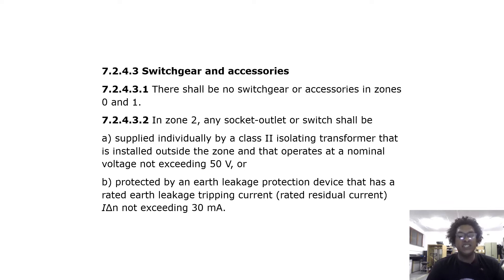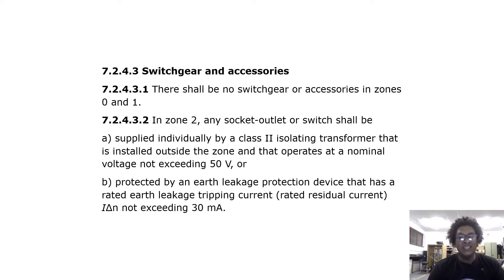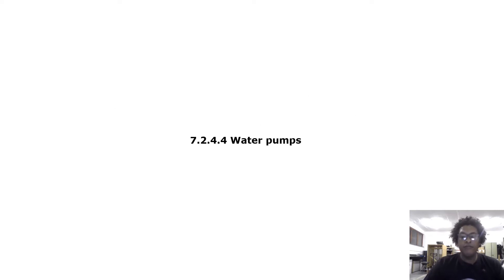There shall be no switchgear or accessories in zones 0 and 1. In zone 2, any socket outlet or switch shall be supplied individually by a Class 2 isolating transformer installed outside the zone, operating at a nominal voltage not exceeding 50 volts, or protected by an earth leakage protection device with a rated residual current not exceeding 30 milliamps.